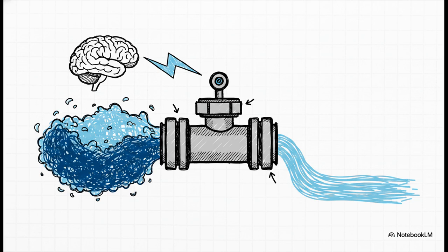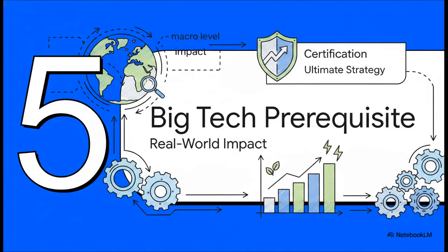When millions of users suddenly prompt an AI, the heat load surges instantly. Old mechanical valves just couldn't keep up. The EEV acts like the hyperfast pulse of the system. Using sensors, it instantly micro-adjusts the flow of refrigerant in response to those heat surges. That stops dangerous liquid from slamming into the compressor, a nightmare called liquid hammering, and keeps everything running hyper-efficiently, no matter what the AI is up to. Which brings us to Section 5, the prerequisite for big tech and the real-world business impact.